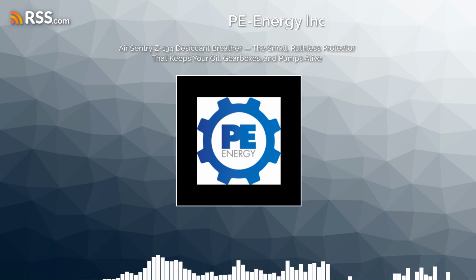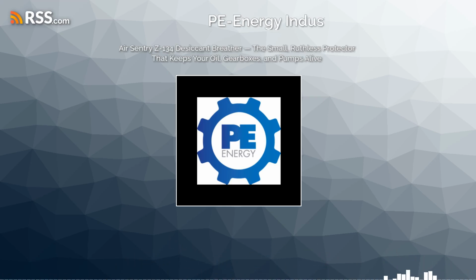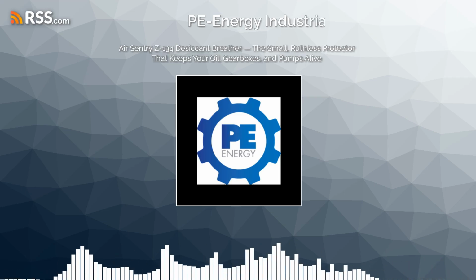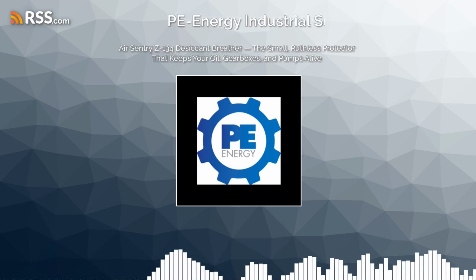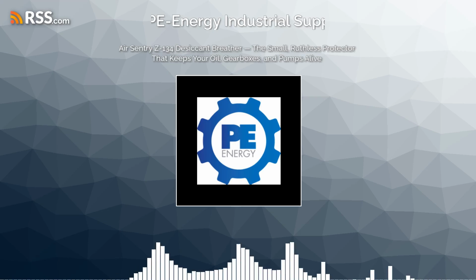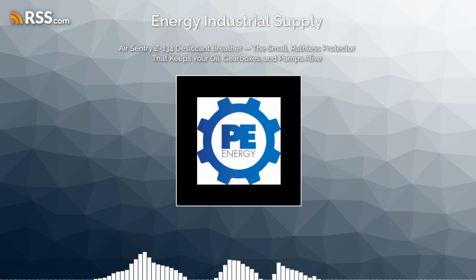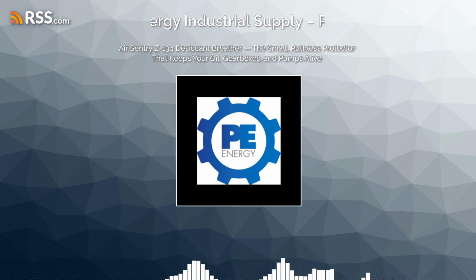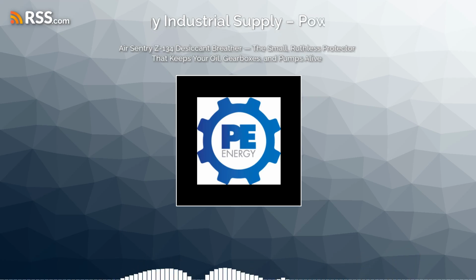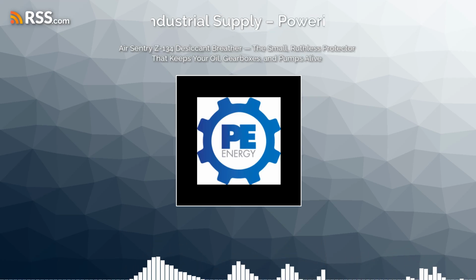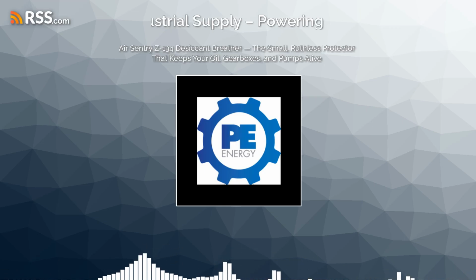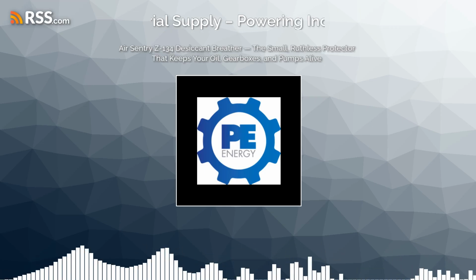And industrial pumps are not designed to pull fluid against a high vacuum on the suction side. Oh, I see where this is going. The first thing that happens is pump cavitation. The localized pressure drop causes the dissolved air and water in the oil to flash into vapor bubbles. When those bubbles pass into the high pressure side of the pump, they implode with incredibly violent force. Like tiny explosions.